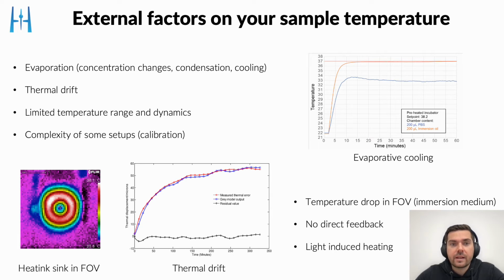There are several external factors that can affect your sample temperature. One effect is evaporation. Due to evaporation, the concentration in the sample volume can change over time. You can have condensation, but also evaporative cooling can heavily affect your sample temperature, just because you have water as a medium that evaporates over time and that cools down the sample volume itself. You can have thermal drifts that move your sample, although you might not want to move it, due to different thermal expansion coefficients of your sample stage, for example.